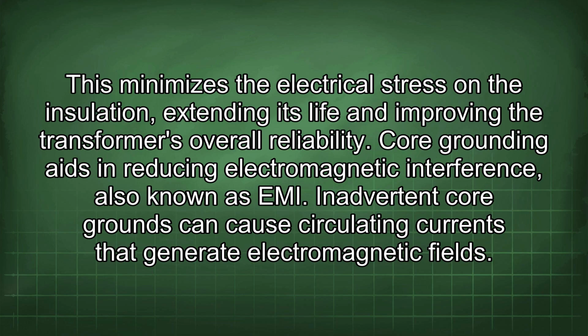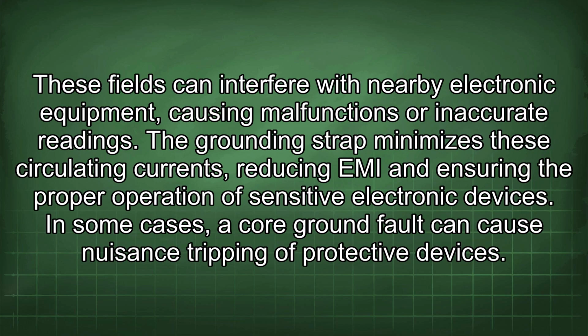Core grounding aids in reducing electromagnetic interference, also known as EMI. Inadvertent core grounds can cause circulating currents that generate electromagnetic fields. These fields can interfere with nearby electronic equipment, causing malfunctions or inaccurate readings. The grounding strap minimizes these circulating currents, reducing EMI and ensuring the proper operation of sensitive electronic devices.